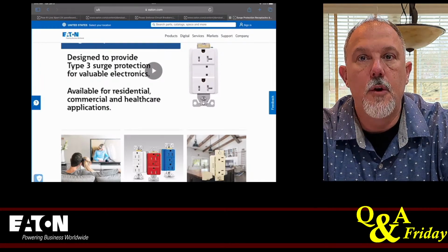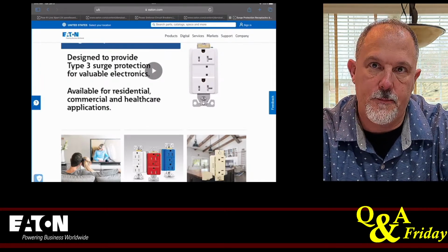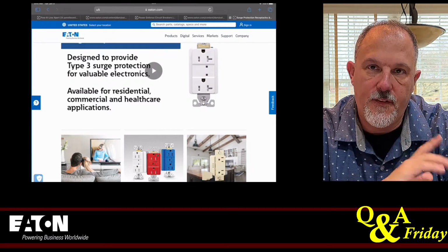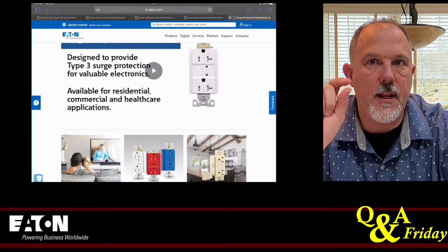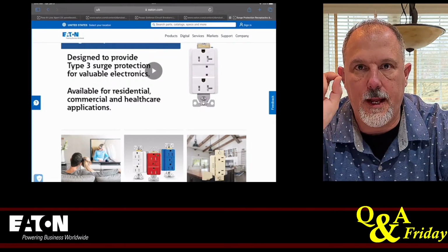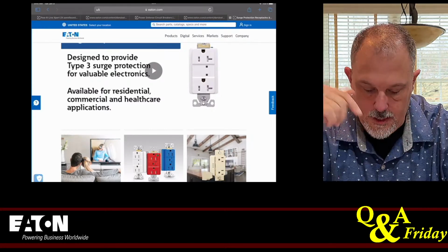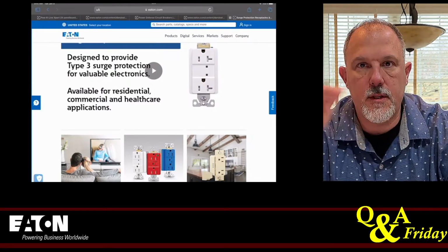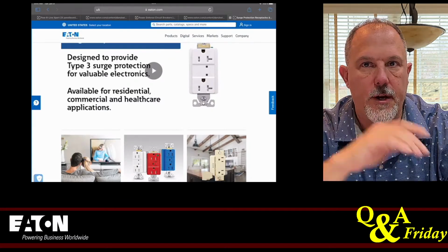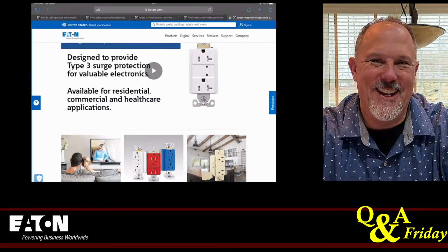You don't have to protect the surge at 15 amps because it's in a 15 amp receptacle. You can use that 15 amp receptacle just as you would in any other receptacle. Put as many as you want. Put those on branch circuits rated 15 or 20.